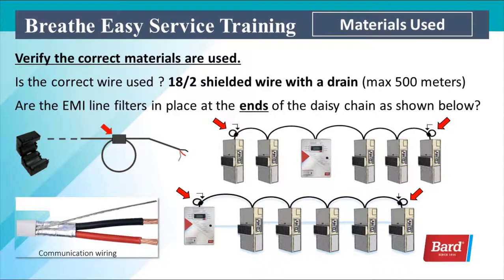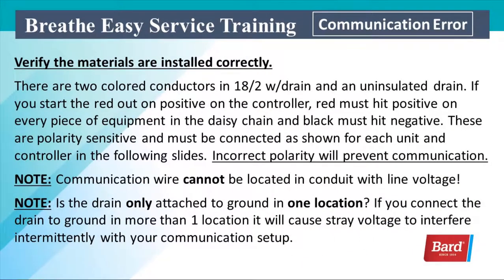Next let's look at the materials used. We need to verify that the correct material is in place: did we use 18/2 shielded with a drain, and is it under 500 meters? Are the EMI line filters in place at the end of the daisy chain as shown? There's one line filter at each end of the daisy chain. It doesn't matter what position the controller is in — it could be in the middle or on the end. In the lower left corner is a picture of our communication wire — this is 18/2 stranded with a shield wrapped around the wires and an exposed drain. To install an EMI filter, simply make a loop with the wire and clamp it — that filter is designed to keep our wire from becoming an antenna.